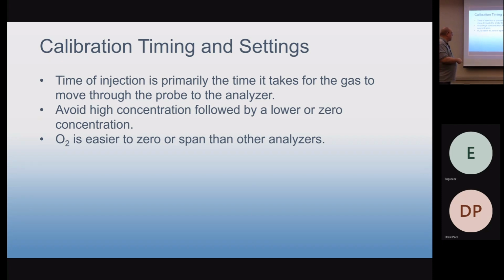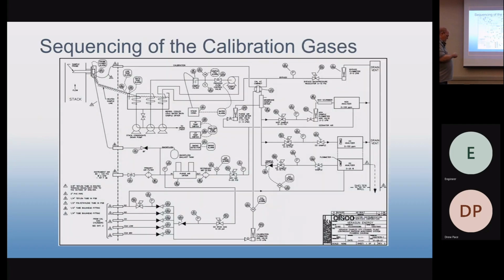On our older systems, I don't think you can read this very good, but you've got a nitrogen cylinder, and then you have a CO and a NOx cylinder, and then you have instrument air that is used. This is a really old system. We don't build them exactly like that anymore. They're real similar, but there's a different philosophy on it. Clif, do you want me to zoom in?